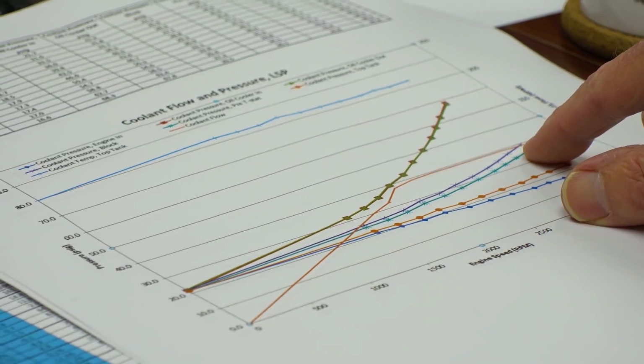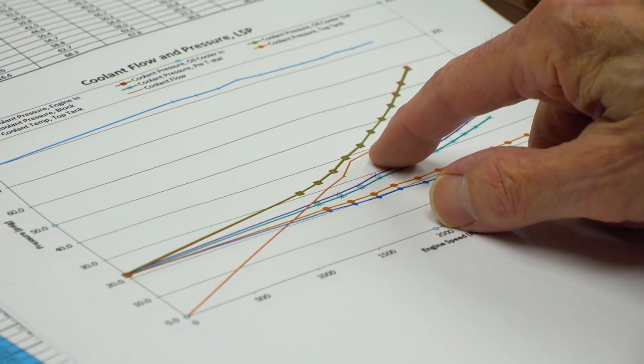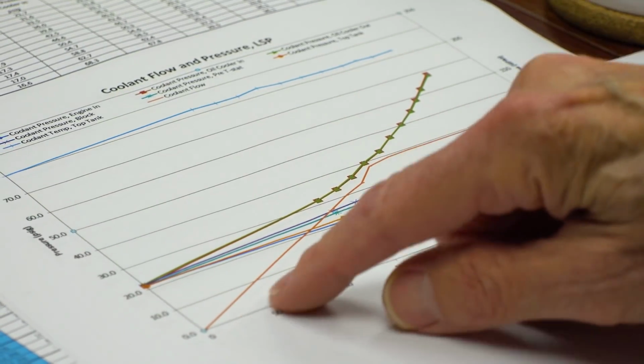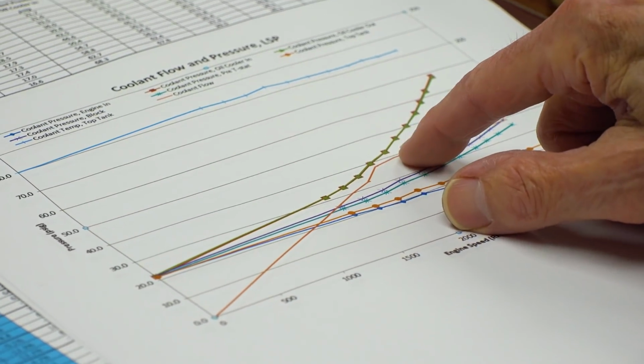Yep. So our 144 gallon per minute flow meter is a 100 gallon per minute flow meter. That's basically what we've got going. In fact, it starts kneeing over right here. So that's probably more like 90 gallons per minute, perhaps. So it's pretty good up to about there, and then it knees over and it's history. If you look at the flow trace, the actual raw data, you can see it's fuzzy as you would expect, but then when it gets up to here, it flatlines.